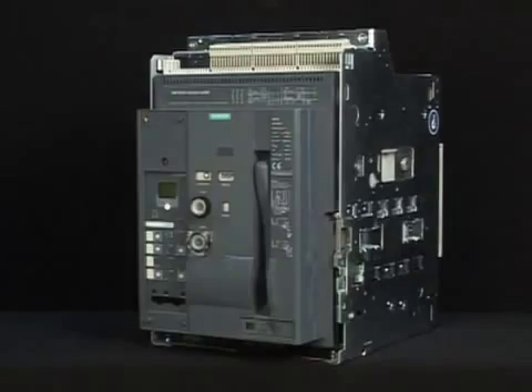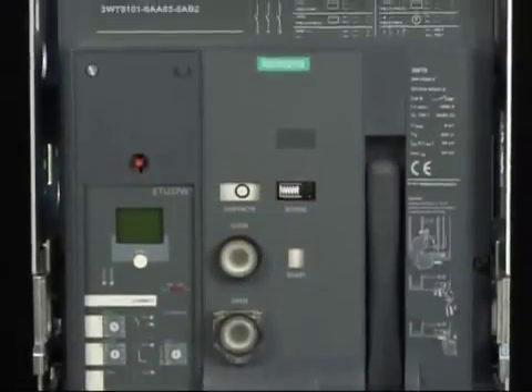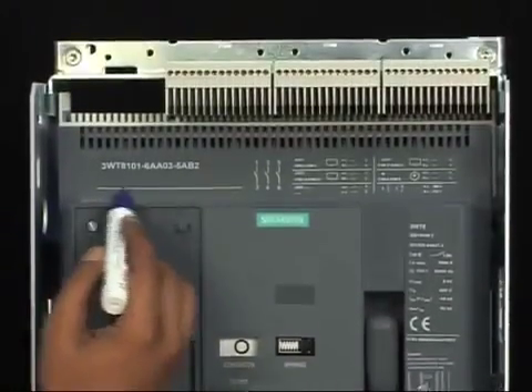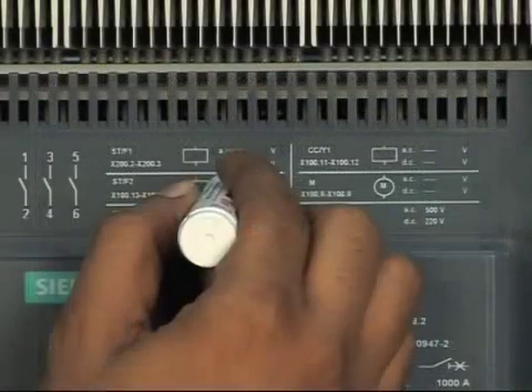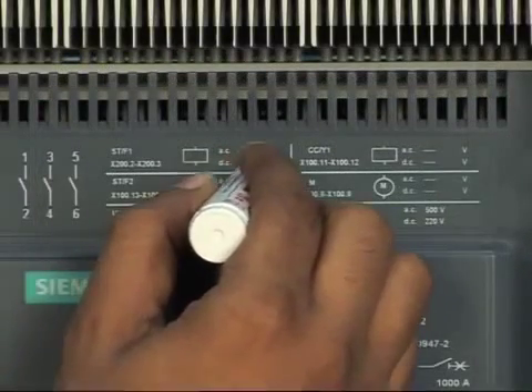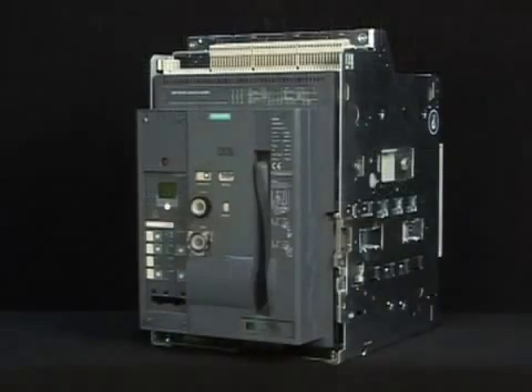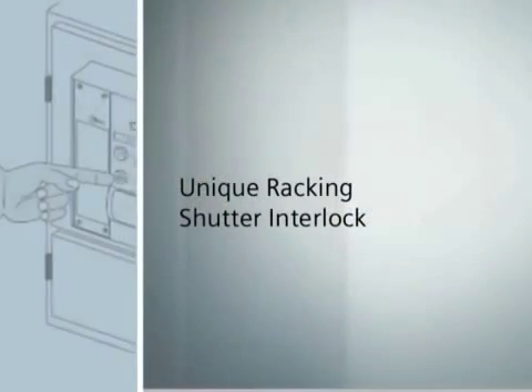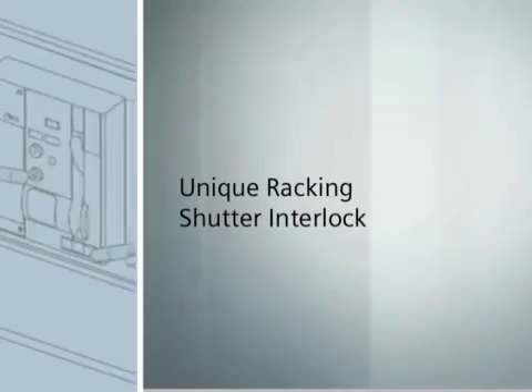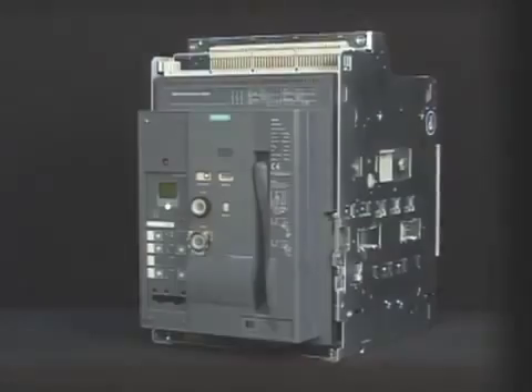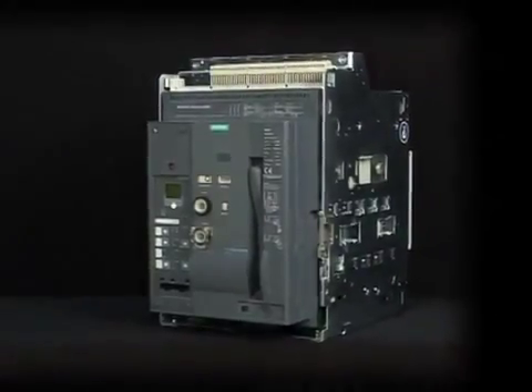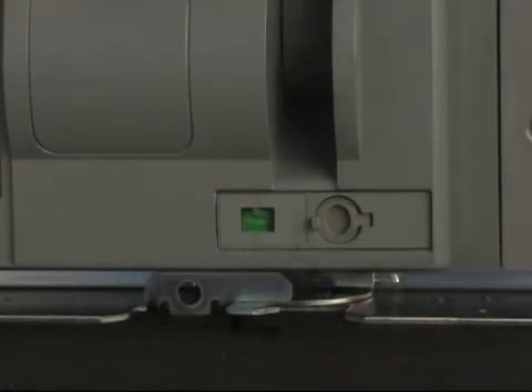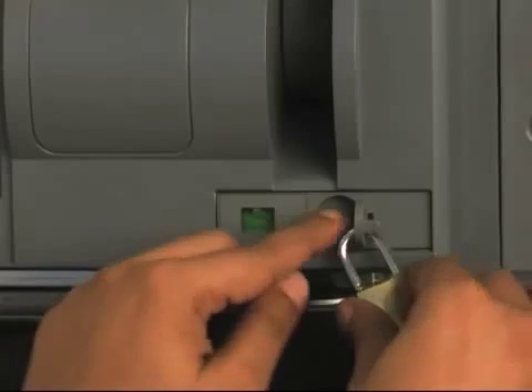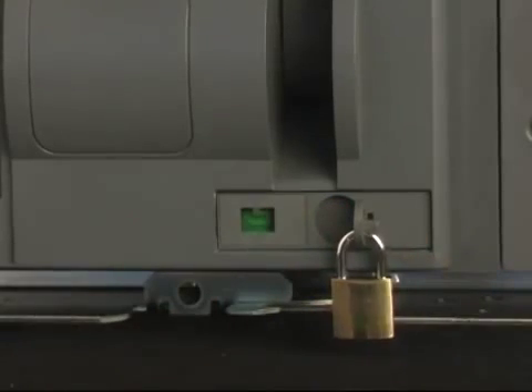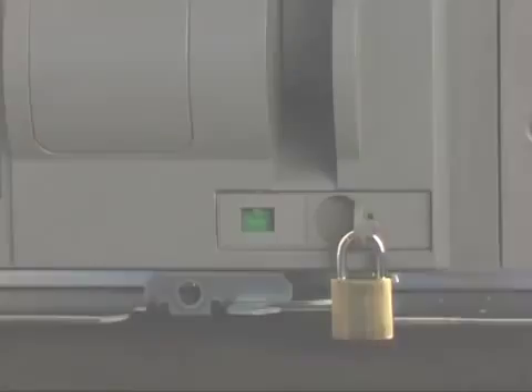After the accessory fitment is done, we recommend immediate editing of the nameplate with indelible ink, or you can ask for a new nameplate. Now, we shall demonstrate another interesting feature of the racking shutter. The racking shutter is provided with a padlocking facility by which it can be padlocked in any of the positions. Once it's padlocked, further racking in and out operation is not possible with the racking handle.